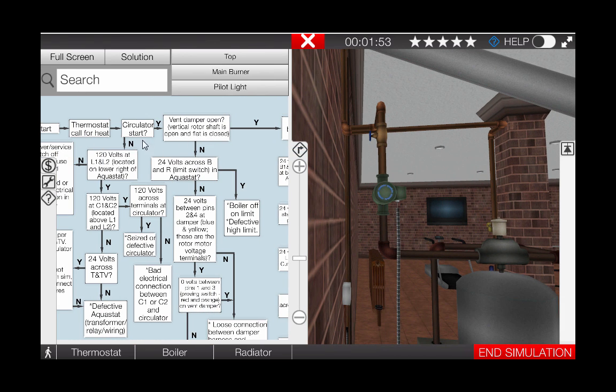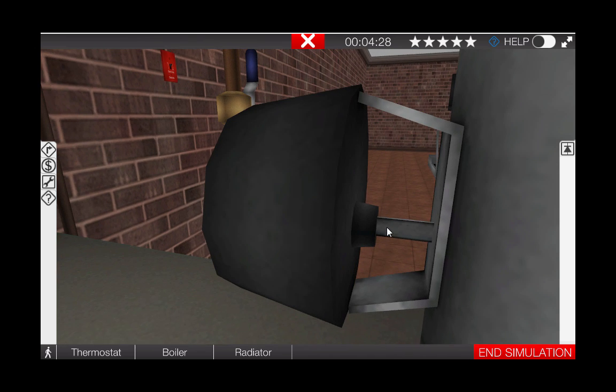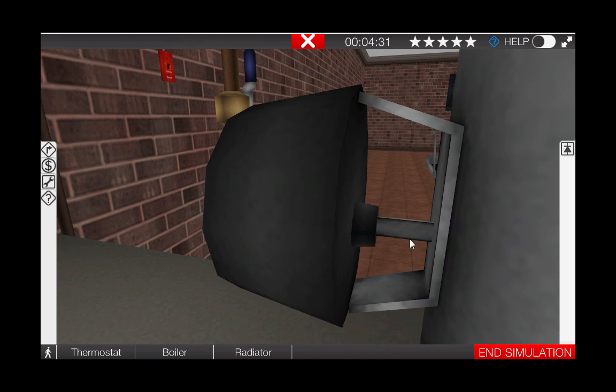As we can see, the circulator did in fact start. Our next step is to check the vent damper. The vent damper is a motorized damper that closes off the flue passage during the burner's off cycle. This prevents heated air from migrating up the flue and chimney and out of the house, and is an important energy conservation addition to any atmospheric boiler. To verify that the vent damper is in fact open, we can look at the position of the shaft. The shaft is vertical, indicating that the damper is open. If the damper was closed, the shaft would be turned flat.